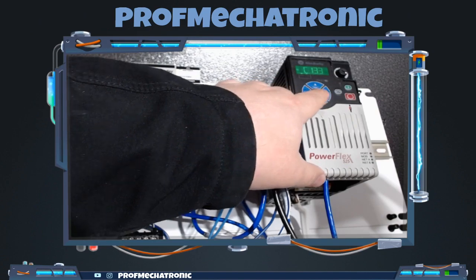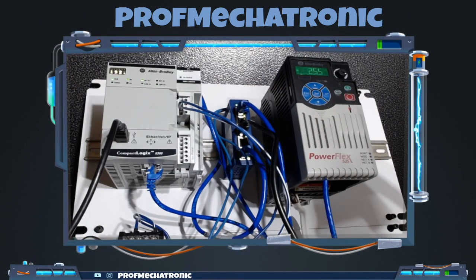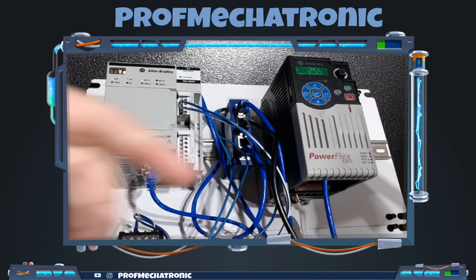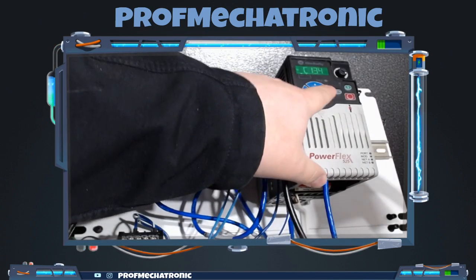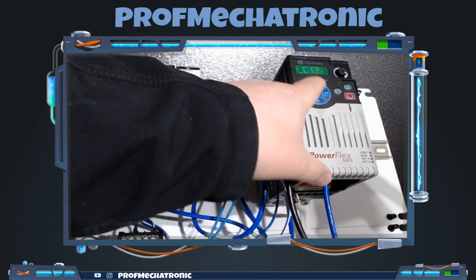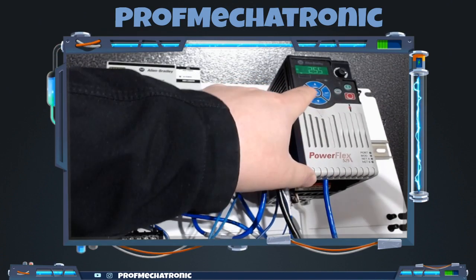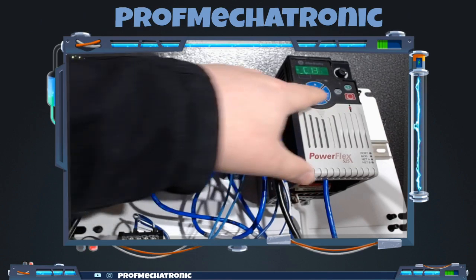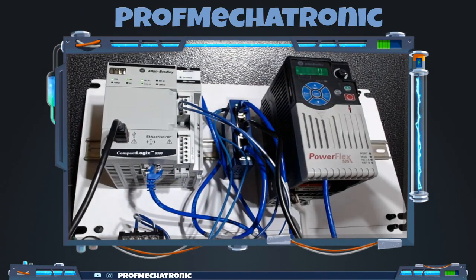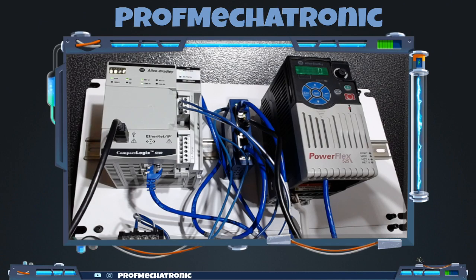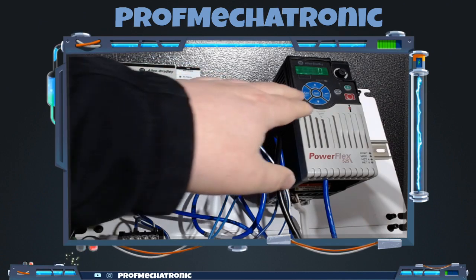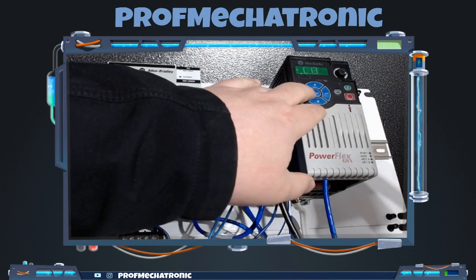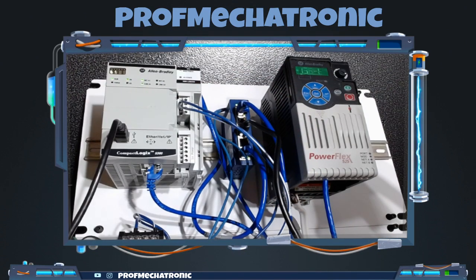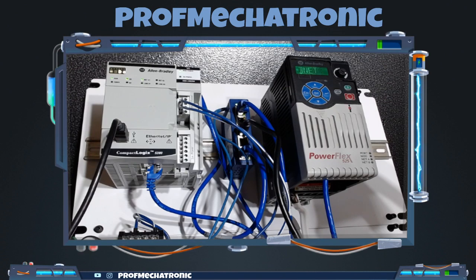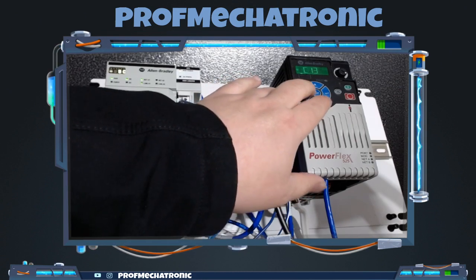Now, when you get into 133, that's what we call the subnet mask. It's very important to set your subnet mask. 133 is your first octet, 134 is your second octet, and 135 is your third octet. You need to make sure your subnet mask matches what you have on your network configuration. Typically, for private networks and most networks we deal with, you're going to leave your subnet at 255.255.255.0. That gives us the basic subnet to allow us to communicate with our PLC, because that's what we have configured on the PLC side.